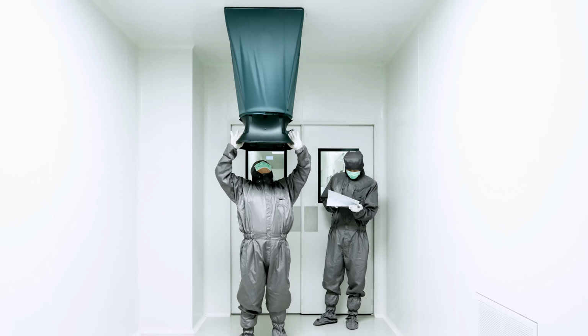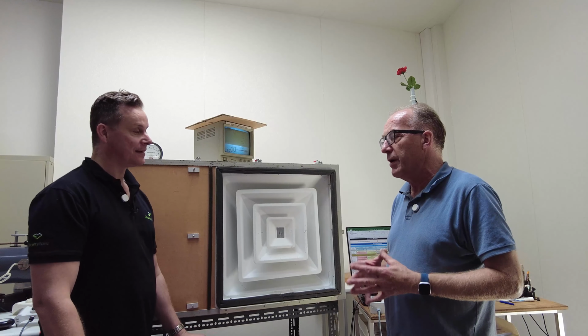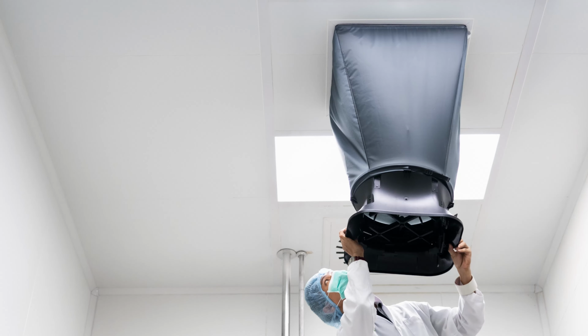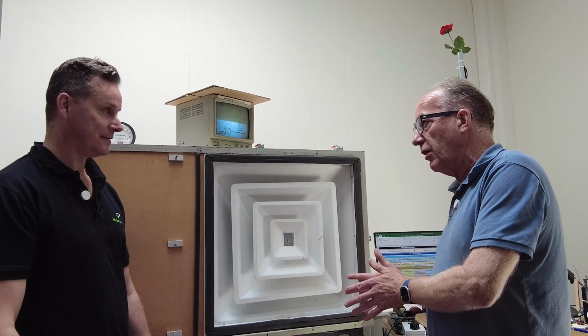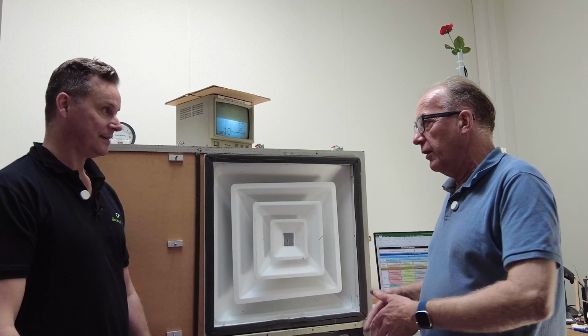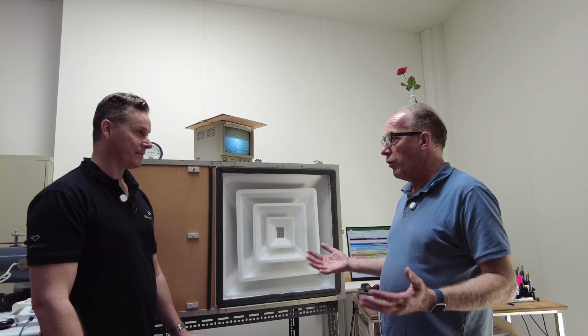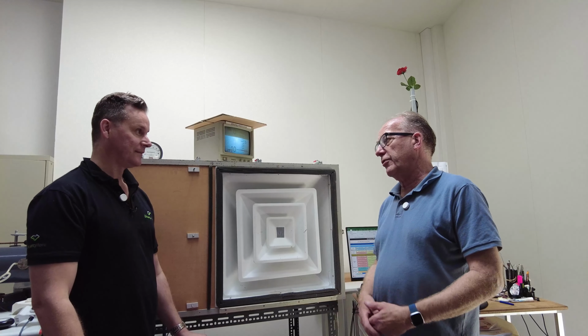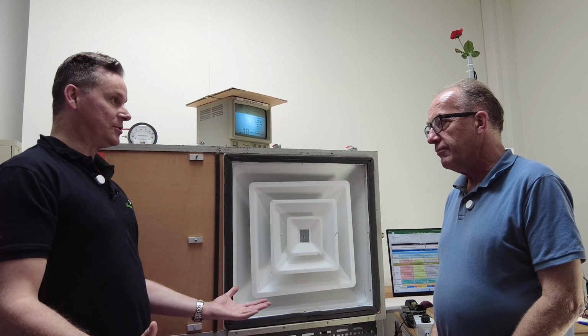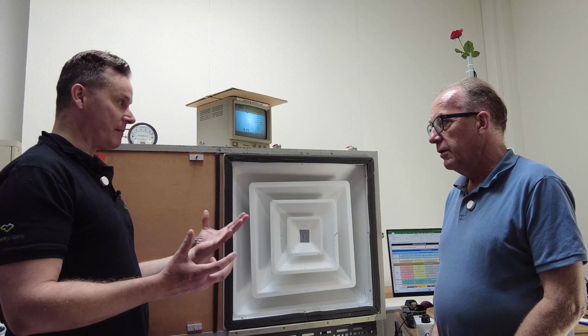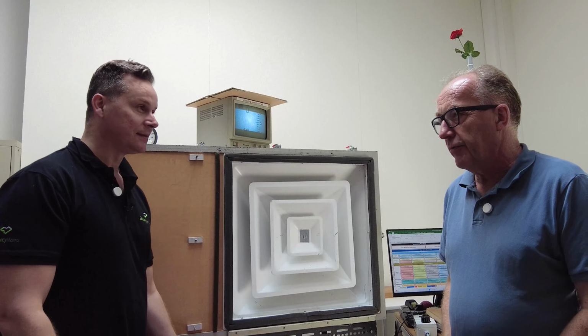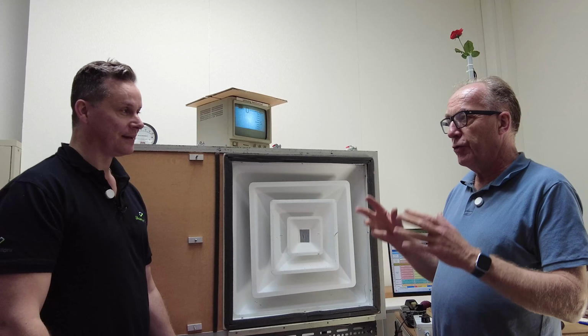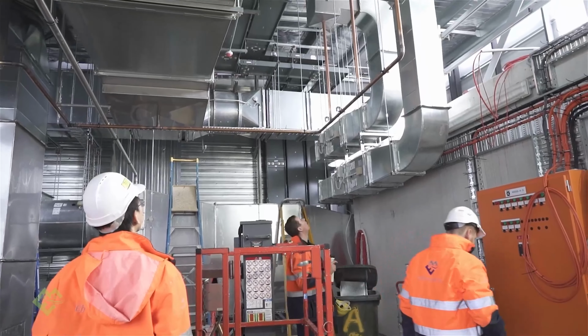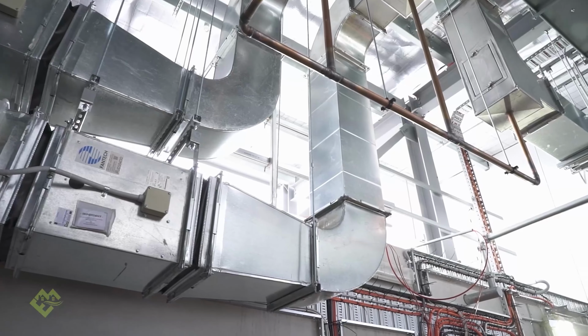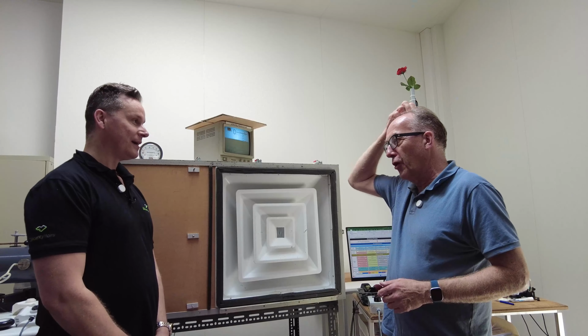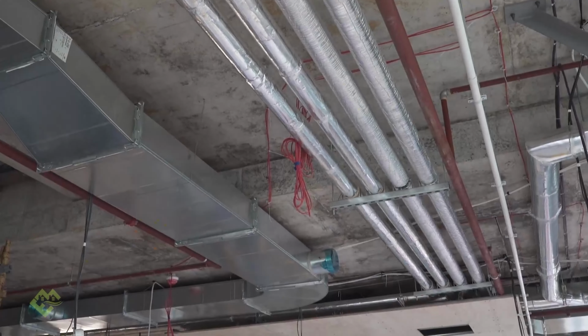Well, we've experienced, especially in the US, it has been shown that in many commissioning jobs, they had a good system to measure the total flow, and they tested it against the Flowfinder, and the Flowfinder and the total flow were in agreement. So our fudge factor is 1. Wow. Which is what you want. Yeah, absolutely. I mean, you just don't need to try and predict where some air may or may not be coming from, right? Well, I mean, you even have a much nicer application. Yes. If you believe in that 1, I do, and the factor is not 1, then you have leakage in your duct system. That's true too. Unless you have a total volume flow which is higher than the sum of the flows. Yes. But that hardly happens.